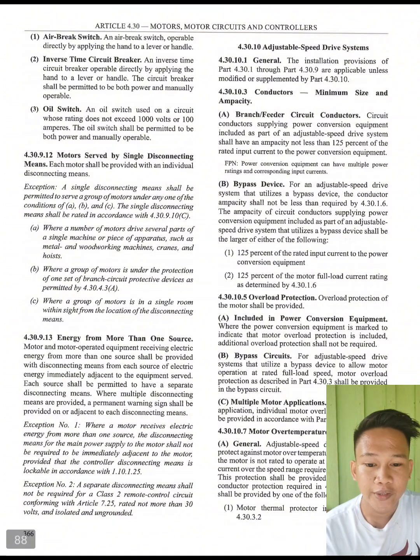So next we have 4.30.9.13. Energy from more than one source. Motor and motor-operated equipment receiving electric energy from more than one source shall be provided with disconnecting means from each source of electric energy immediately adjacent to the equipment served. Each source shall be permitted to have separate disconnecting means where multiple disconnecting means are provided. A permanent warning shall be provided on or adjacent to each disconnecting means.